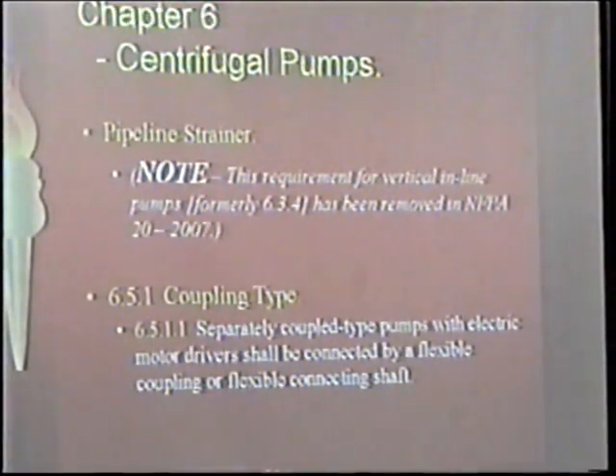This is something that was eliminated out of the code, and we've been talking about this for the last, I don't know, five years it's been in the code, six years maybe, the last two code cycles, about a pipeline strainer being installed before any fire pump where you had to remove the motor in order to inspect the impeller, which meant an inline type pump. You'd have to have a pipeline strainer ahead of it. Well, now they've eliminated that requirement. Nobody ever put one in anyway. Well, there's two in Minnesota.